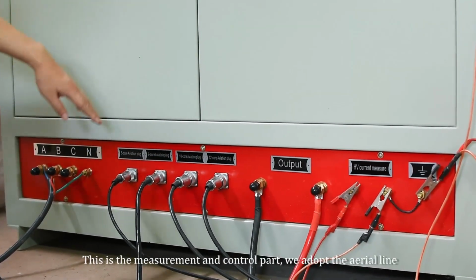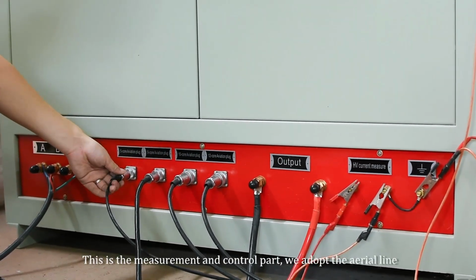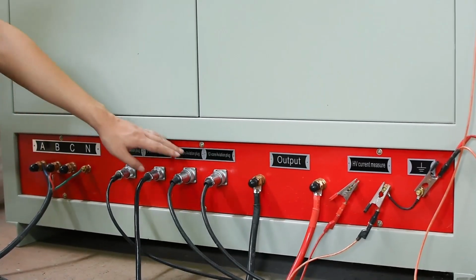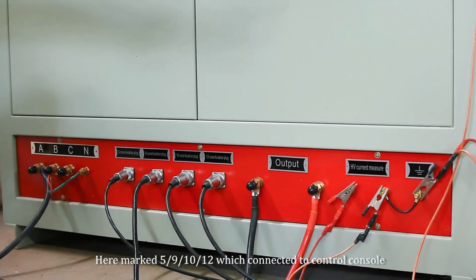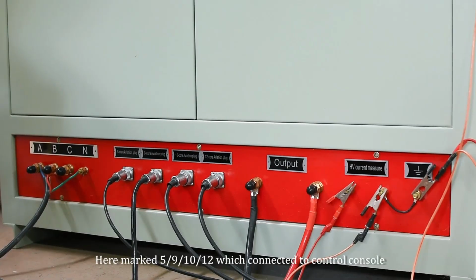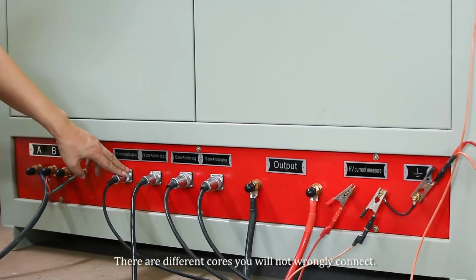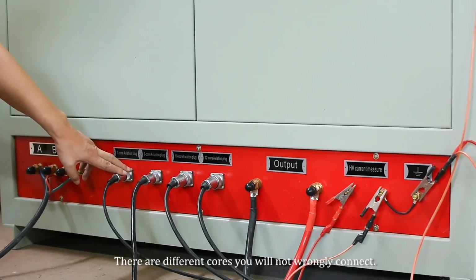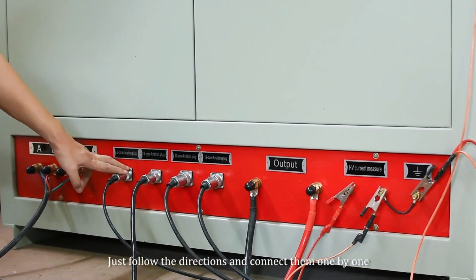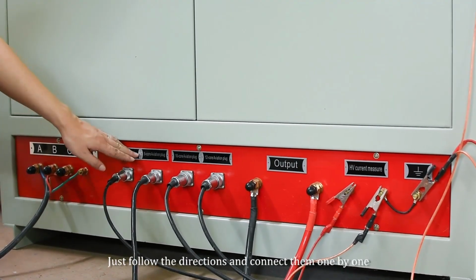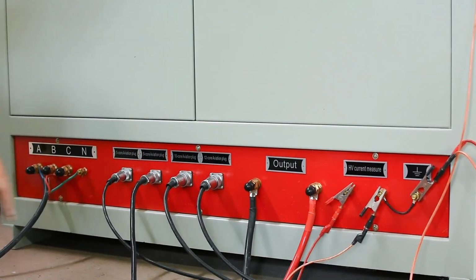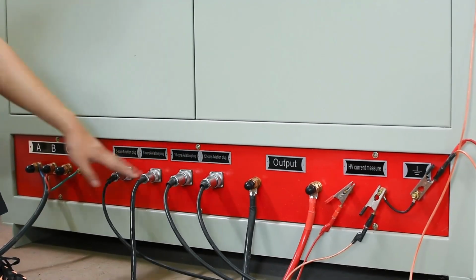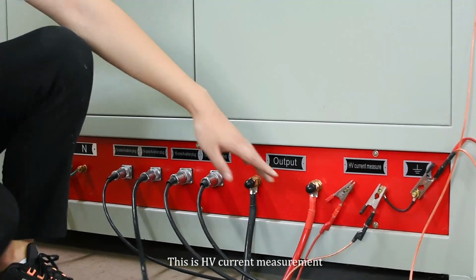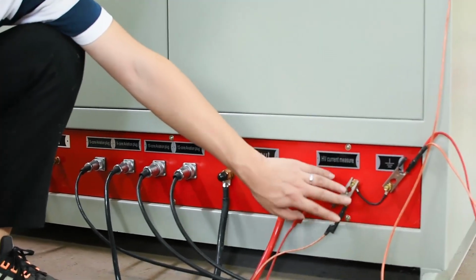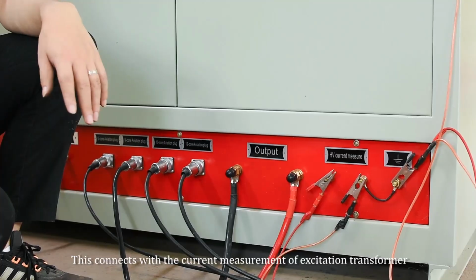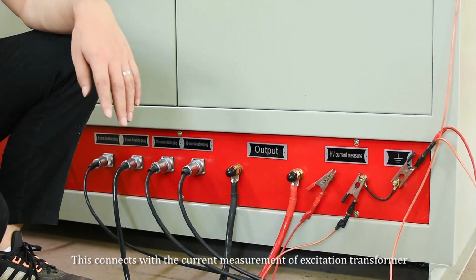This is the measurement and control part. We adopt the aerial line. Here marked 5, 9, 10, 12, which are connected to the control console. There are different cores, so you will not wrongly connect. Just follow the directions and connect them one by one. This is HV current measurement. This connects with the current measurement of the excitation transformer.